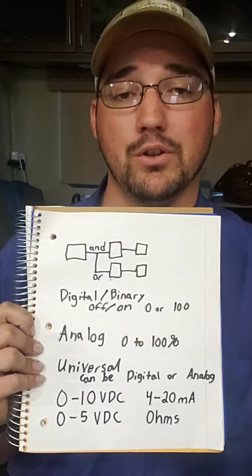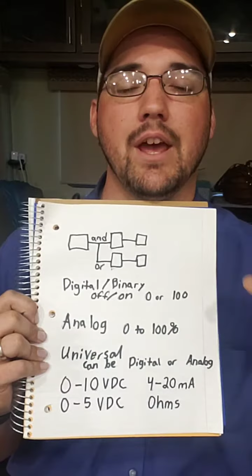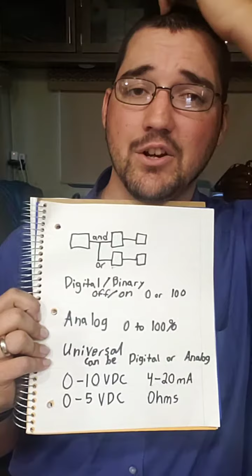A big thing about digital and binary outputs, not inputs but outputs, is that the outputs themselves are typically an actual relay. There'll be a legitimate relay built into the controller that controls the output signal going out. So the controller fires that relay and closes it. Sitting here now, I kind of wish I had a controller in front of me so I could show you a little better, but that's okay. So those are your three main inputs and outputs you're going to run into.